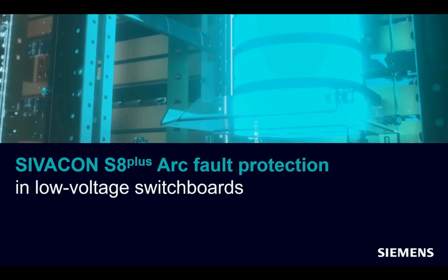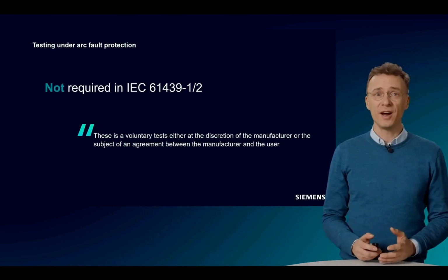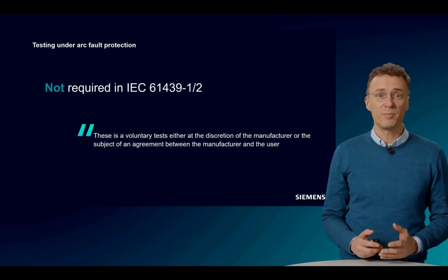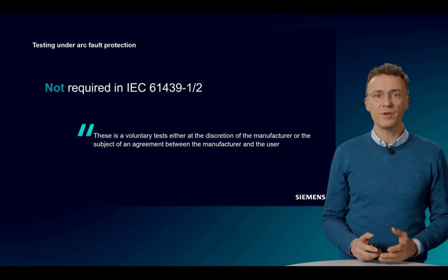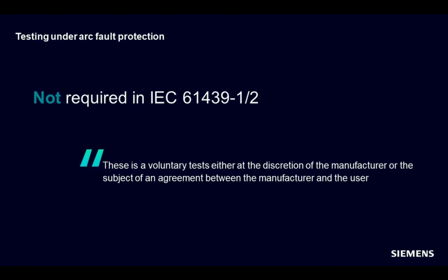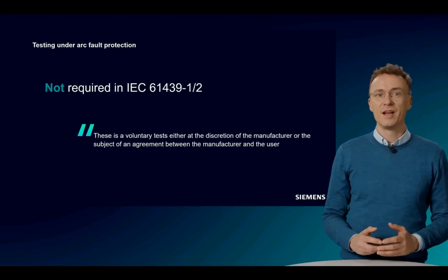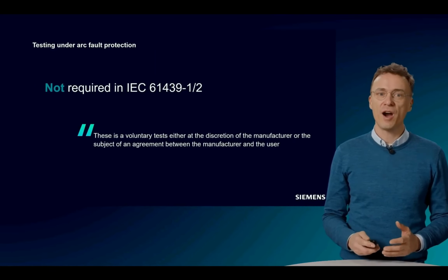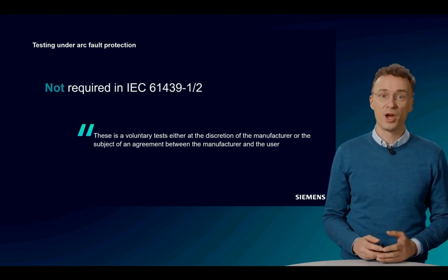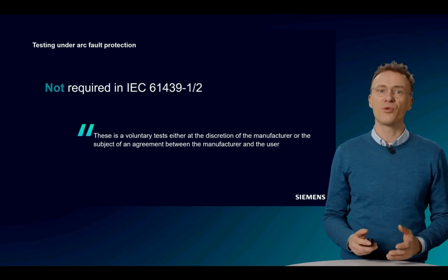Low voltage switchboard is produced in accordance with IEC 61439-2. This regulates, for example, the topic of degree of protection, internal separation, and the design verification, but also the subject of arc fault protection. The standard defines the requirements for the construction and behavior of the switchboard. However, the behavior in the event of an arc fault is explicitly not covered by this. The requirements for the behavior under condition of arcing are regulated in a technical report, which is not part of the IEC 61439-2.